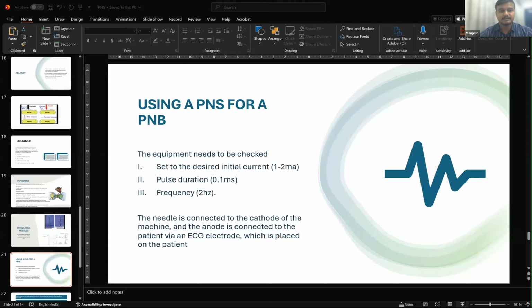So, as we discussed, the stimulating needles and the tip. The equipment needs to be checked. That is, it has to be set to a desired initial current of 1 to 2 milliamperes and a pulse duration of 0.1 milliseconds with the frequency of 2.